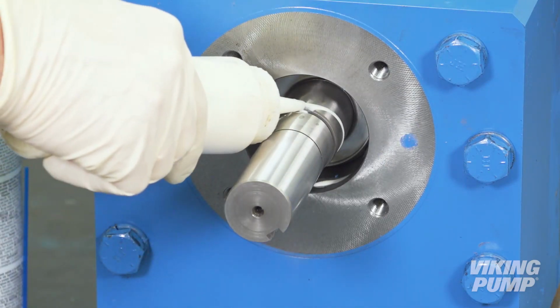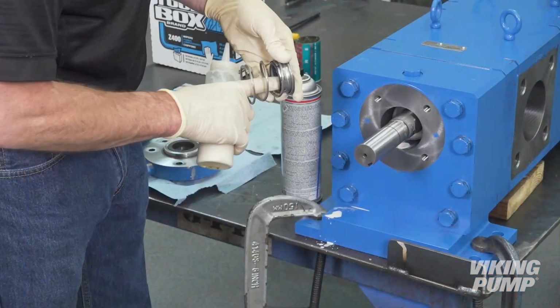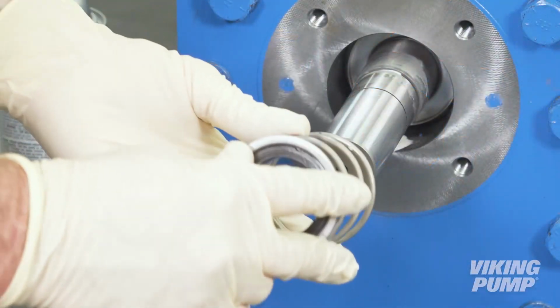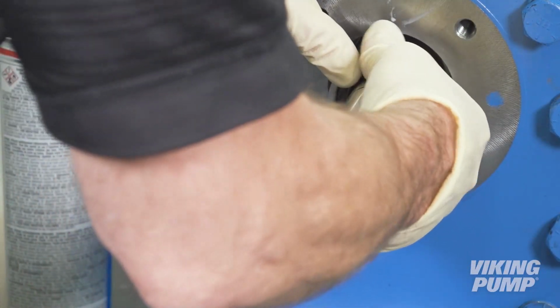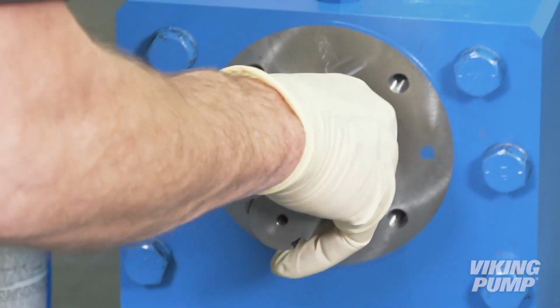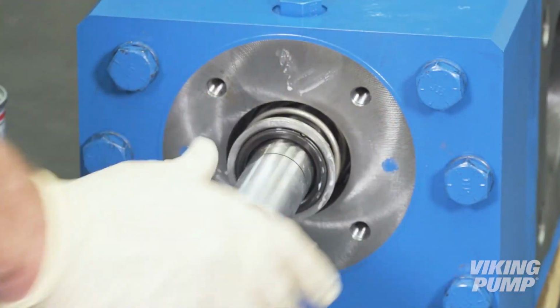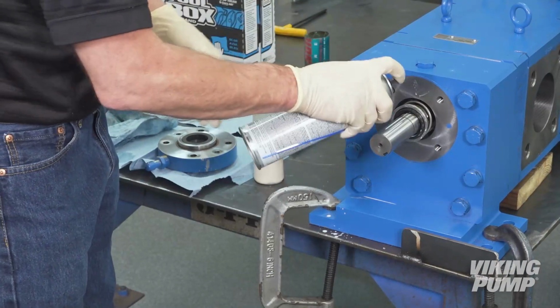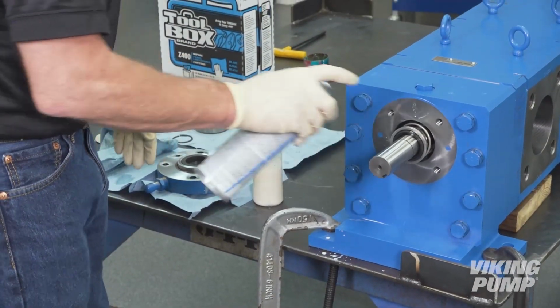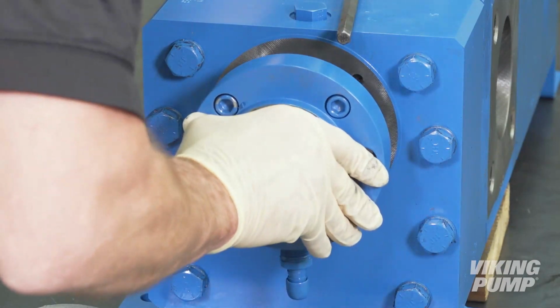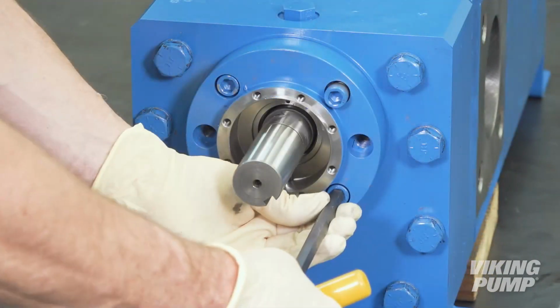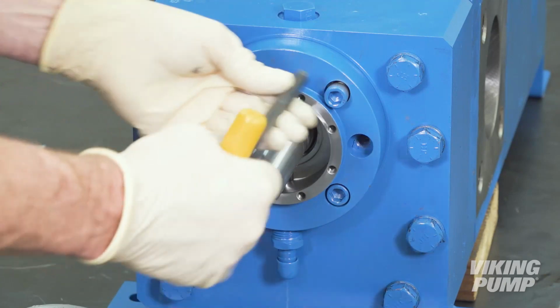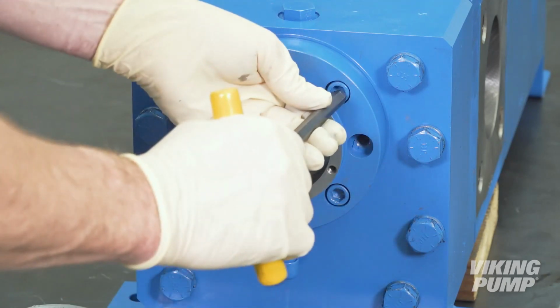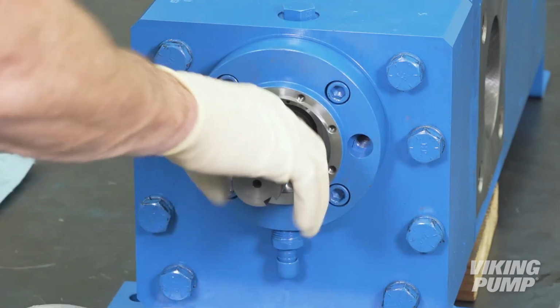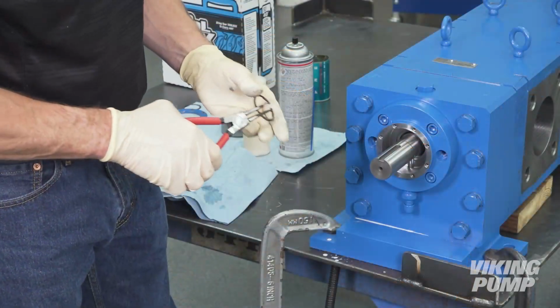Coat the shaft and the inner diameter of the mechanical seal with P80 lubricant and install. Make sure the seal spring is fully seated within the spring guide. Clean the seal faces with a lint-free cloth and isopropyl alcohol or another suitable cleaner. Install the seal holder assembly with the seal housing drain in the 6 o'clock position and tighten the cap screws in a star pattern. Turn the pump input shaft by hand to check for free rotation. Install the retaining ring into the groove on the shaft.